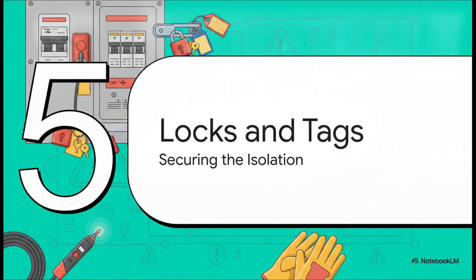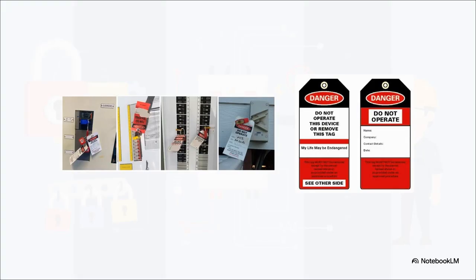Okay, Section 5. Securing with locks and tags. Whenever you do not have sole, effective control of the isolation device at all times, meaning you can't physically see it or someone else could easily access it, you absolutely must fit that device with a physical locking mechanism and a warning tag. This is exactly what stops someone from accidentally returning power while you're literally elbow deep in a board. And if a whole team is working, every single person must attach their own personal lock.